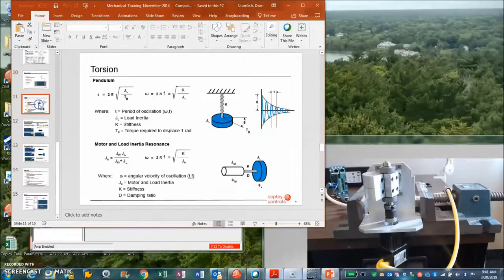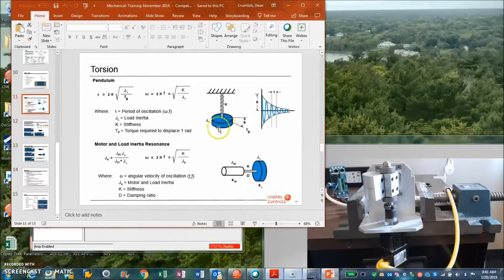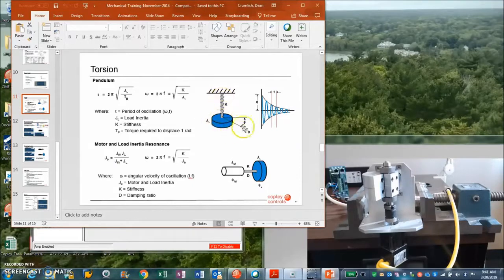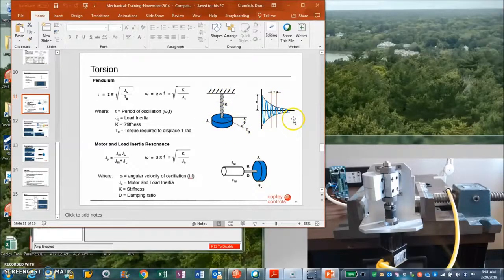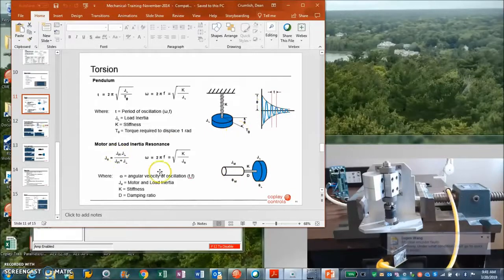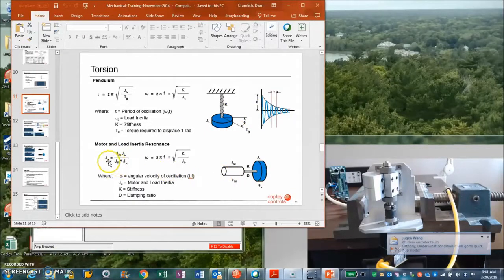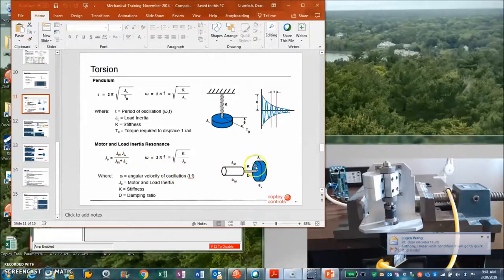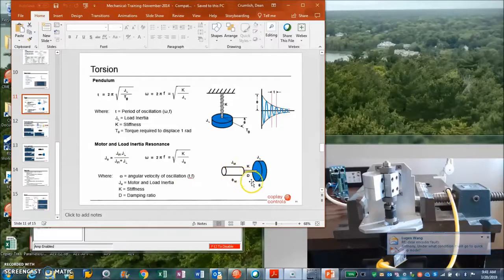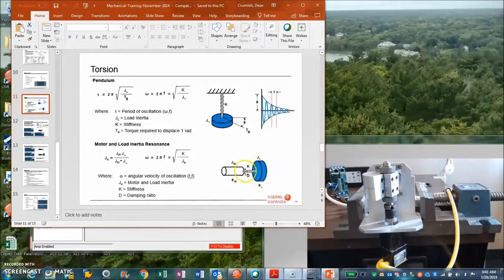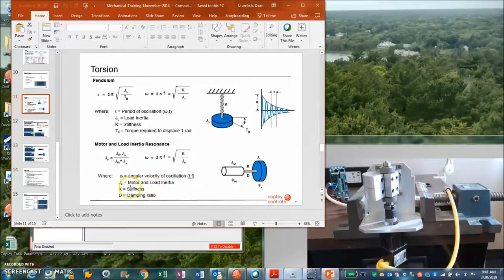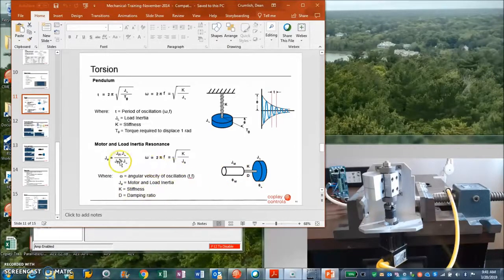Check to make sure you're not voltage limited constantly—a little bump on your head's fine. Watch the following error, check the settling time. But back to the inertia thing again: I have like a disc with a spring, and I wind it up and I let go and it bounces. Same thing as this old mechanical system is with the new inertia matching. I have a motor inertia; if you hold the shaft and turn the load and let go, you'll see a bounce that's defined by the torsional stiffness.